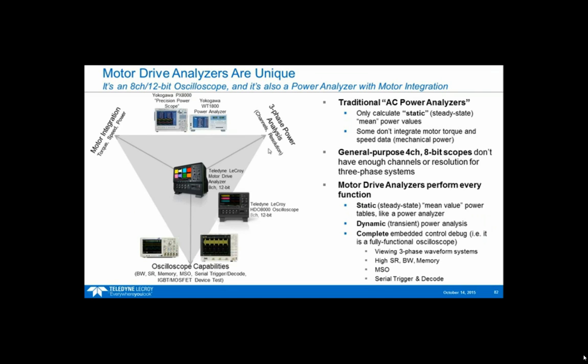If we come back and look at how the capability sets compare, this probably makes more sense now. You've got 3-phase electrical power analysis and motor power analysis, which power analyzers typically and historically have done. For everything else, whether it's device analysis or embedded control system test, scopes have done that. But the motor drive analyzer sits in the middle — it does all these different things. It has 8 channels, 12 bits, it's a scope that also has power analysis capability. Based on the combination of all the inputs and tools, we've built in the ability to do very unique dynamic or transient power analysis and correlate all those activities back to embedded control system behaviors. So it's more than just one of these and one of these together — it gives you a lot more capability.